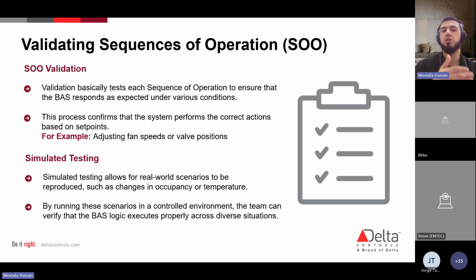Now, simulated testing, as you mentioned earlier, you can play the scenario before it gets to the field. You can run simulations on controllers before they actually make it into the field. You can simulate certain conditions, changes in temperature, humidity, demand variations, right? You can run these scenarios in a controlled environment before it makes it out into the field.